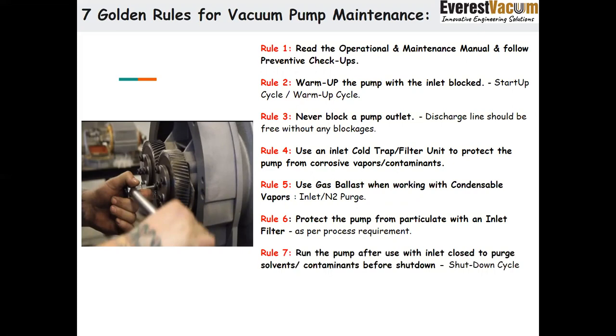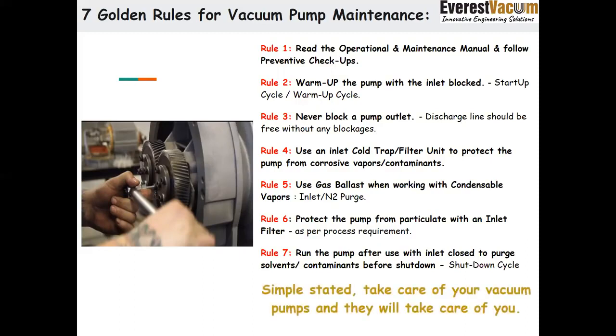And rule 7 is to run the pump after use with the inlet closed to purge solvent contaminants before shutdown. The shutdown cycle has to be thoroughly followed. It is already pre-programmed for everyone's ease. The only thing requested is that we do not press the emergency button and instead operate it via the stop button. So simply stated, take care of your vacuum pumps and they'll take care of you.